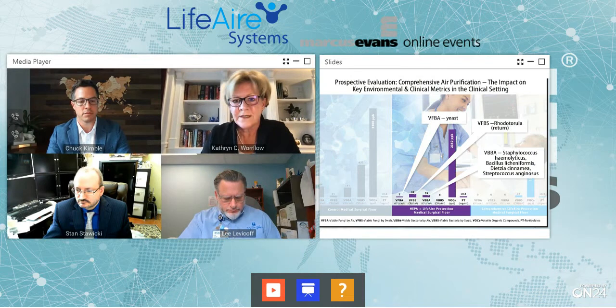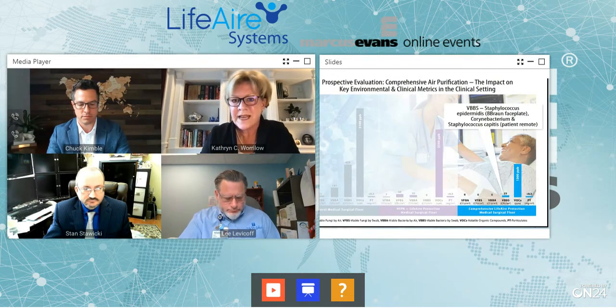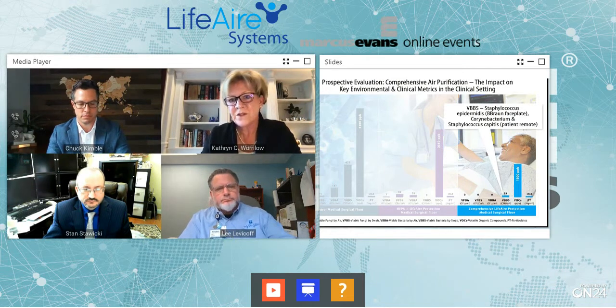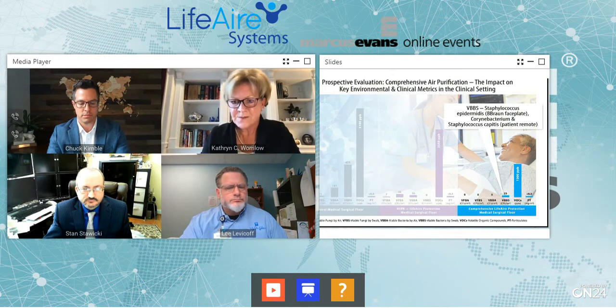If you look at Zone A, which was completely protected, supply and return air, by the LifeAire system, we have 0 viable fungi by air, 0 viable bacteria by air. And again, that's monthly testing for 12 months. Because of the reduction of your airborne loading, you have a significant reduction in your viable fungi by surface, as well as your viable bacteria by surface. What was found were 2 forms of staph, one on the IV control plate and the other on the patient remote, probably related to touch.